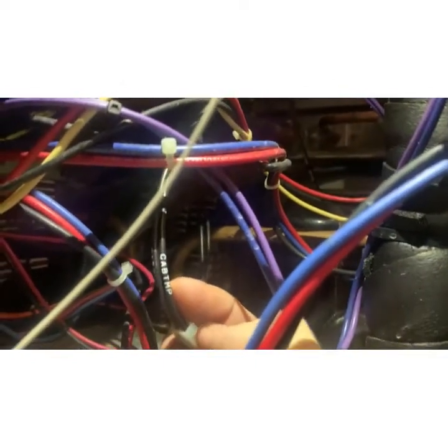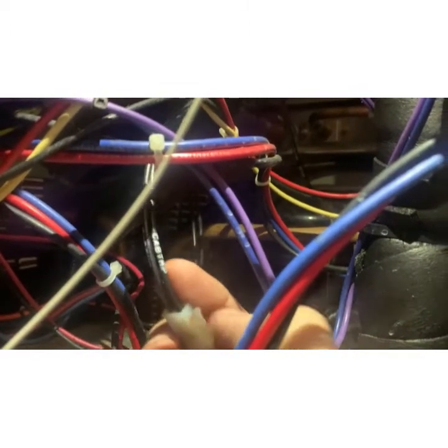So that cable right here - fingers out of the way - that black one that runs into the cabinet, I'm going to assume is the cabinet probe. It runs up to a Molex connector right here. Look at how great Electro Freeze is on this one - the cable says 'cab temp.' Solid. That's definitely our probe.